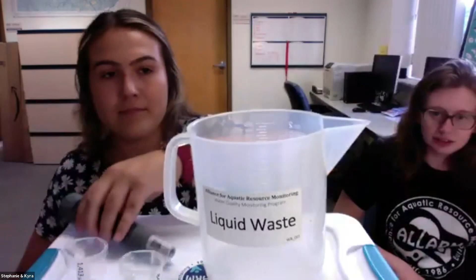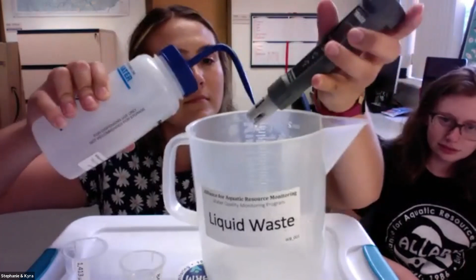We have 84 calibrated to the low range. That's fantastic. For those of you with shale or sandstone, you're going to have values in that low range, so it's important we calibrate to that. Okay, so now that we have successfully calibrated to the 84, we're going to rinse the electrode with distilled water over the waste container and shake dry. And since we've all successfully calibrated to 84, you can dump that 84 solution into your waste bucket and put that vial and your standard off to the side.